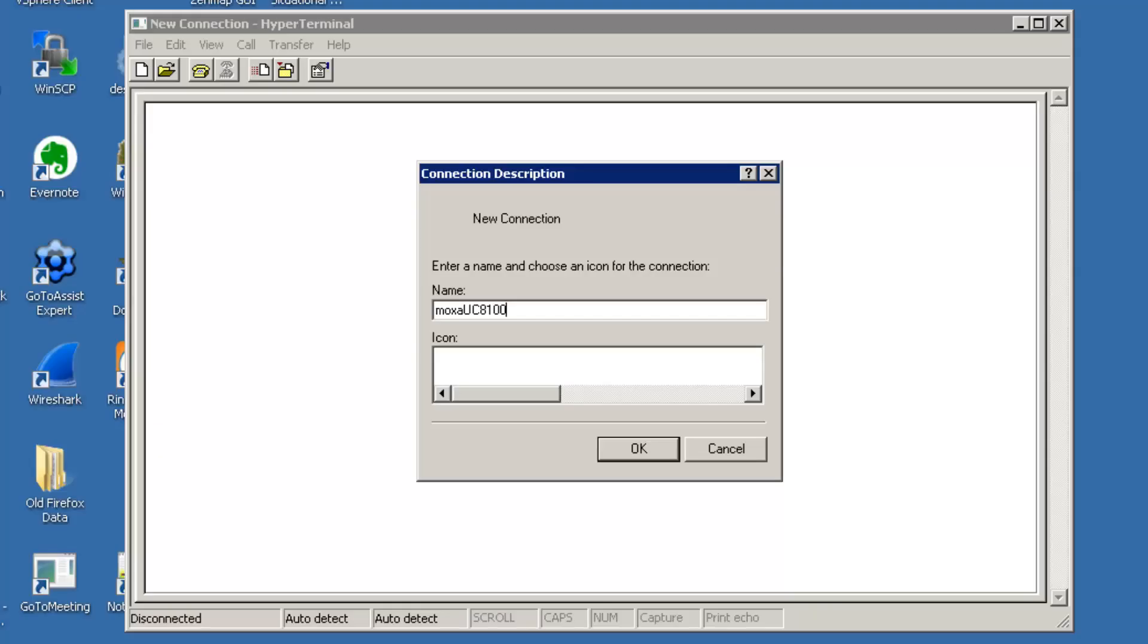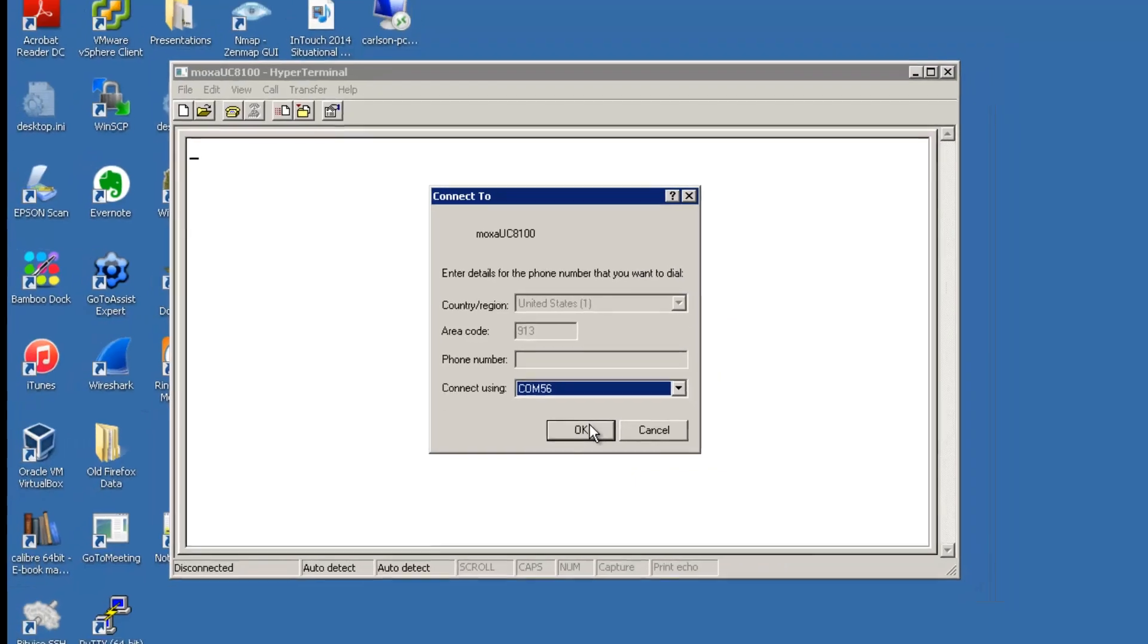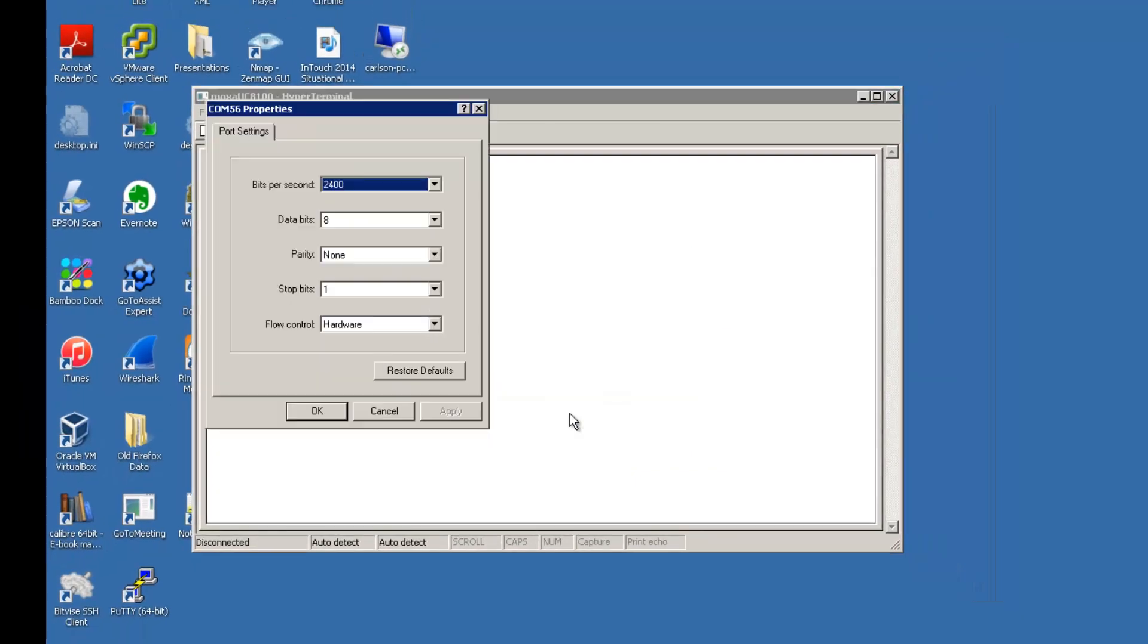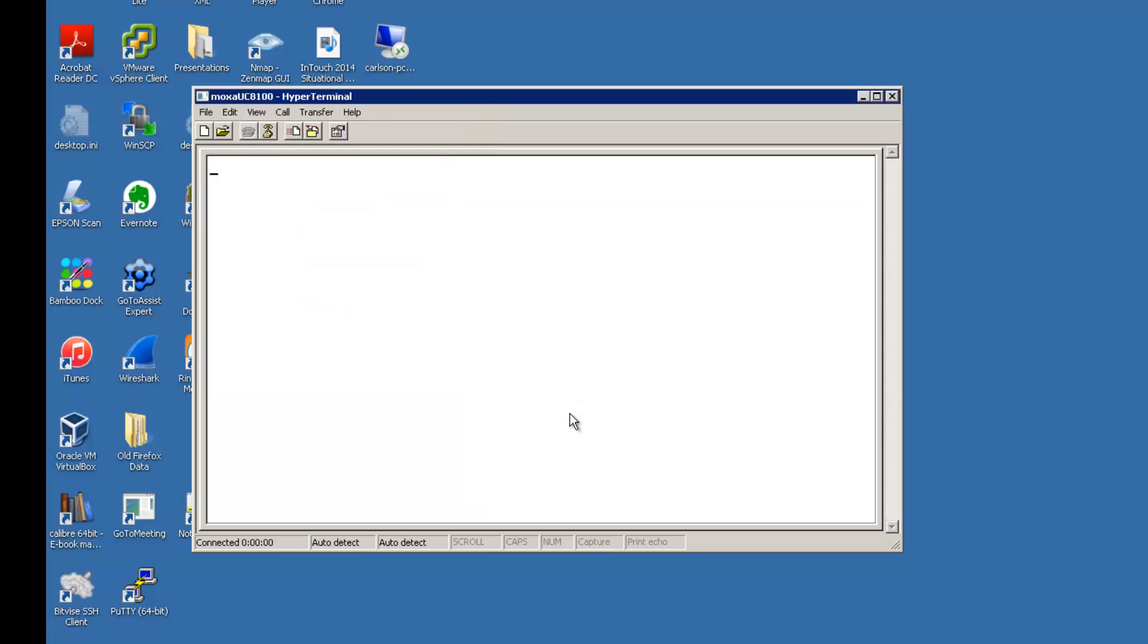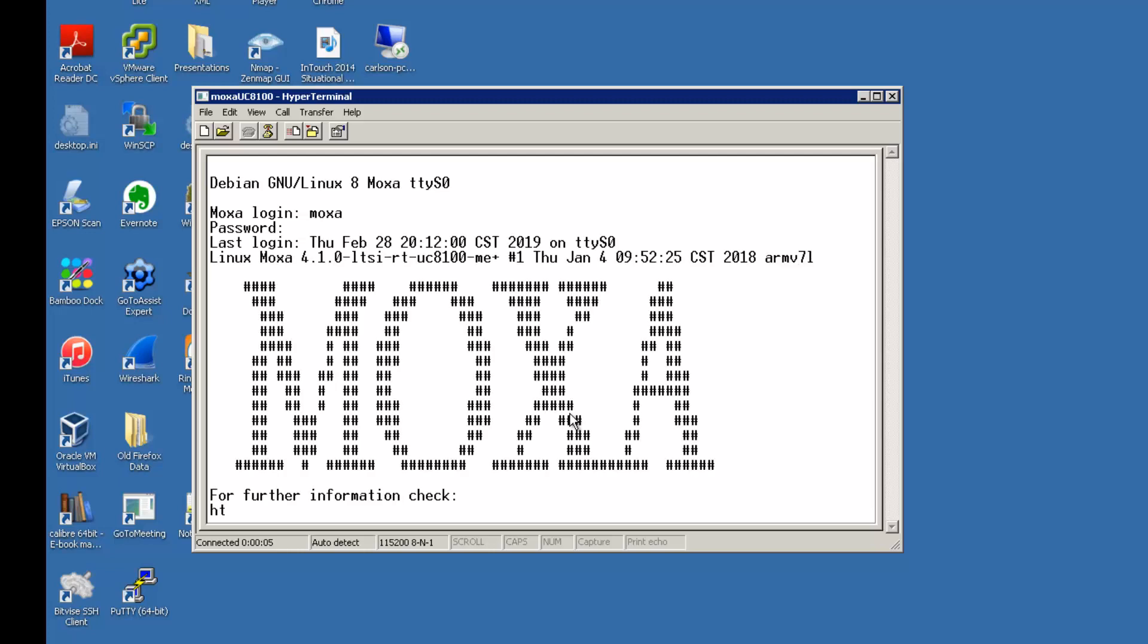So now we've got our Moxa UC-8100 powered up and I'm connected via the console cable to the serial port on the unit. We're going to use HyperTerminal to go in and change the settings and get it on our network. Here's the console port settings. The default login is Moxa and Moxa.